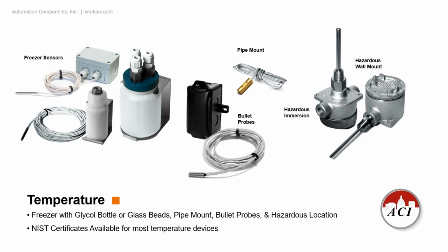It's basically a thermal buffer. So when you're opening and closing the freezer doors, it doesn't set an alarm. It'll take a couple minutes if it's dampered by the glycol or glass bead solution that the sensor goes into, that bottle and secures to.